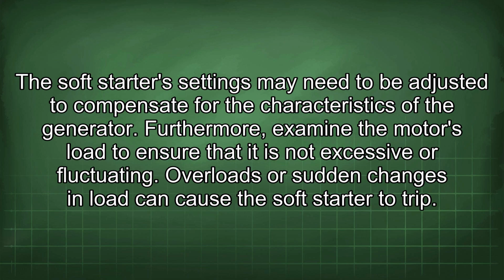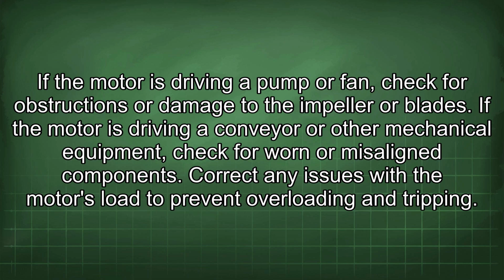Furthermore, examine the motor's load to ensure that it is not excessive or fluctuating. Overloads or sudden changes in load can cause the soft starter to trip. If the motor is driving a pump or fan, check for obstructions or damage to the impeller or blades. If the motor is driving a conveyor or other mechanical equipment, check for worn or misaligned components. Correct any issues with the motor's load to prevent overloading and tripping.